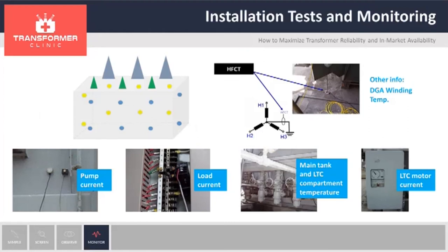That was the explanation for screening testing. If we go with the next two steps — diagnostic testing and online monitoring — this is the typical setup. We have sensors on the transformer on the four walls of the unit, installed in service. We have magnetic temperature sensors, clamp-on CTs for load current, tap-changer current, pump current, and we also add a high-frequency CT connected either to the tank ground or the neutral ground connection. All this installation is done in approximately four to six hours, so it's a very fast installation process.